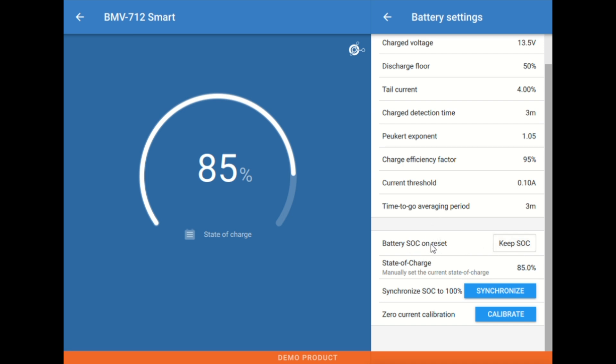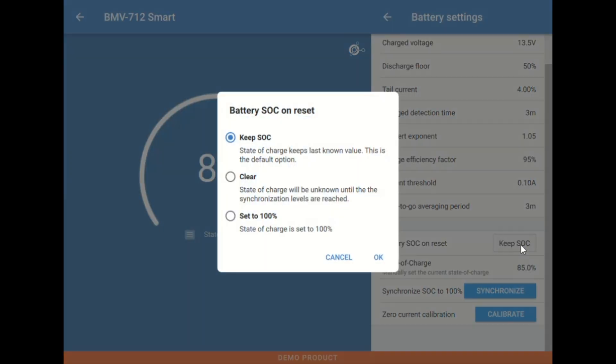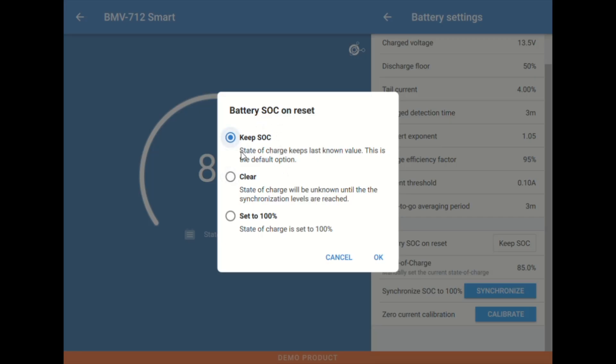Below that we're going to look at this next value. This is usually something we like to adjust. This battery SOC on reset, typically we're going to want to set this to keep SOC. That way if the meter is powered down for any reason or is reset, it's going to remember the last percentage value rather than clearing or setting to 100%.